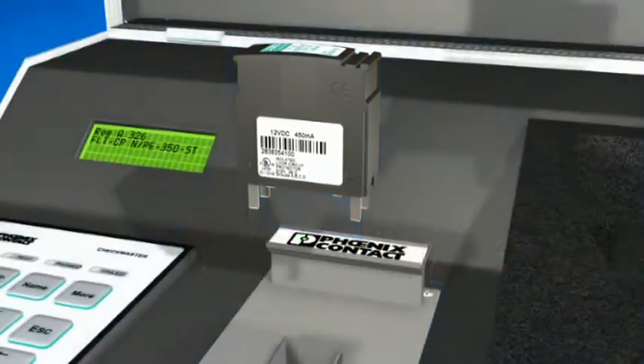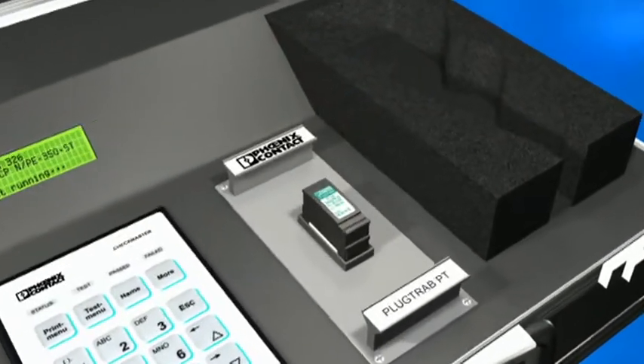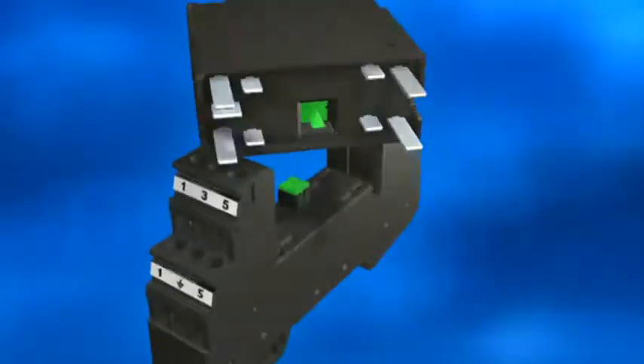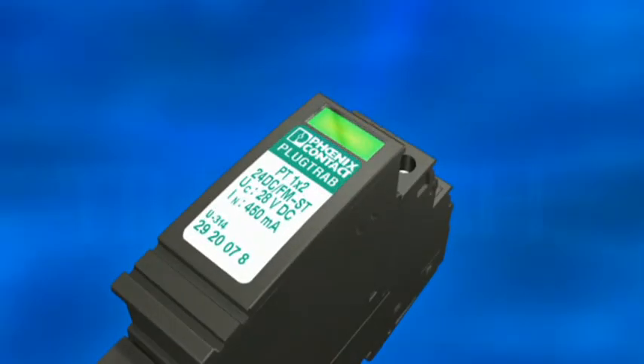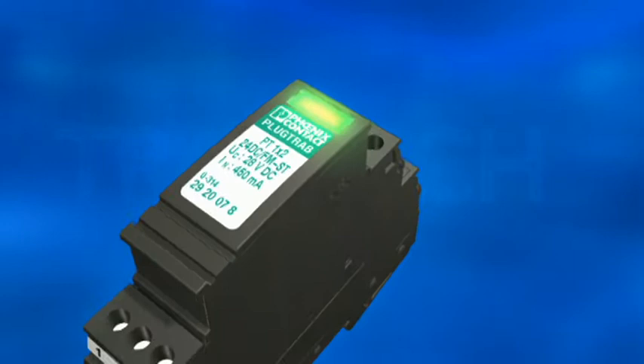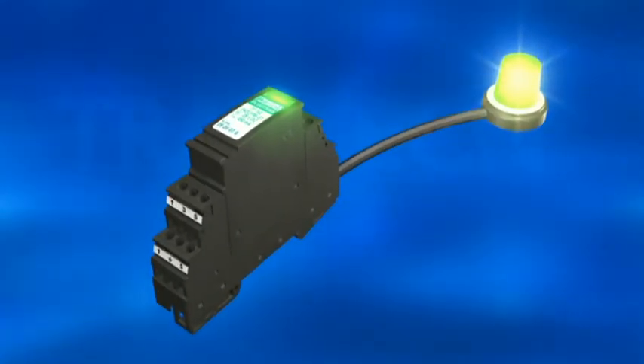Arrestors can be checked in advance using the Checkmaster without modifying the signal circuit's impedance and are coded automatically. New features for Plugtrab include the built-in function display and floating remote indication contact for monitoring from the system.